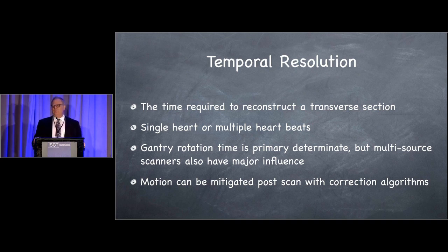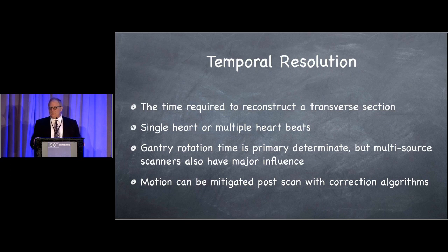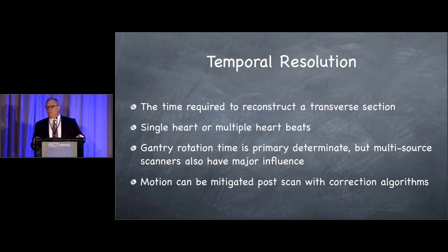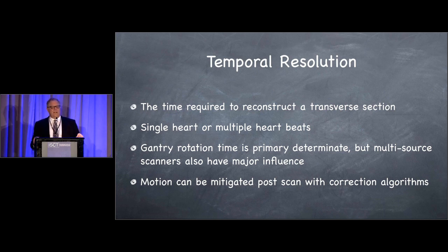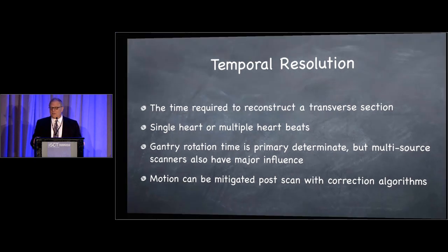Temporal resolution is defined as the time required in order to create a transverse reconstruction — to collect the data for a transverse section. The temporal resolution can be applied to scans that require a single heartbeat or scans that require multiple heartbeats. The gantry rotation time is the primary determinant, but multi-source scanners also have a major influence. It's also worth recognizing that motion can be mitigated post-scan with dedicated correction algorithms.